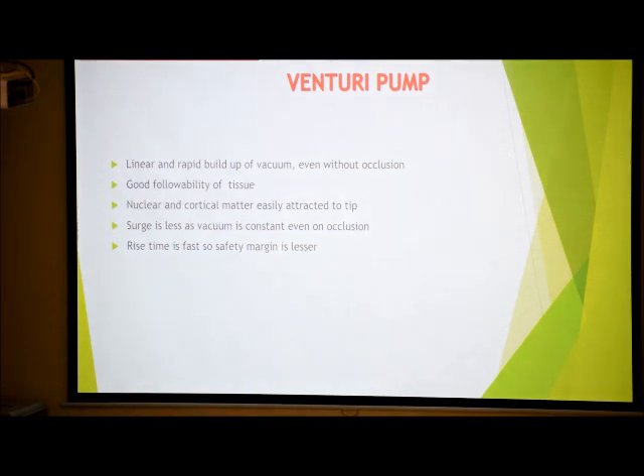Linear, rapid build-up of vacuum even without occlusion. Followability of tissue is very good. Nuclear cortical matter is easily attracted to the tip. Surge is less because there is no deviation from the standard preset vacuum level. Rise time is fast, so the safety margin is less; more advisable for a skilled surgeon.